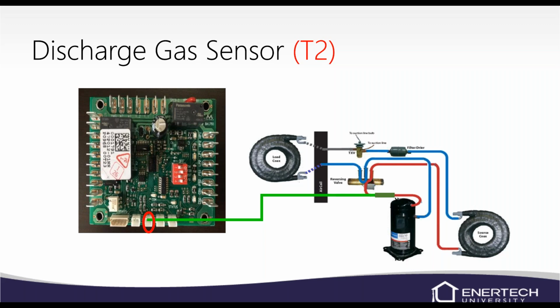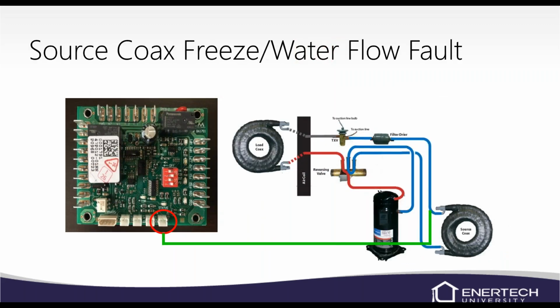Discharge gas sensor, that's a T2 sensor, and it's located on the discharge gas line of the compressor. It will lock it out if it's higher than 220 degrees for more than 30 seconds. Again, source coax water flow or freeze fault, again, that's that T4 sensor. And depending on the dip switch is going to decide whether you're looking at the sensor or the flow switch.